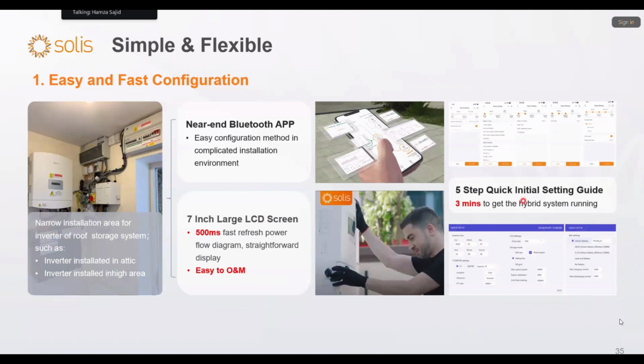Then we have a quick setup initial settings guide. In the first step, it is going to ask you for the time and date, then whether you are using a CT or a meter. Then the grid standard and your utilization scenario, like storage mode: are you going to use self-use, selling first, or off-grid? These 5 or 6 things you set up, and the inverter is going to be in running condition.